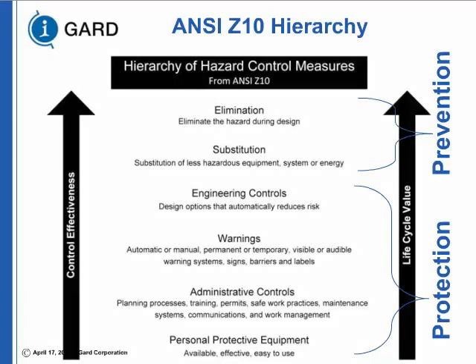Very surprisingly, industry data indicates a human is prone to error 1 in 10 times. If the same operation is done 10 times, he or she can make an error 1 time out of 10, which is a very high percentage. As opposed to engineering control, a relay has a 1 in 1,000. The PLCs we use for electrical safety are 1 in 100,000. So you can see why it is beneficial not to depend on warnings, administrative control, and PPE. I would not say not to depend totally, because for an existing installation, that may be the only choice you have.